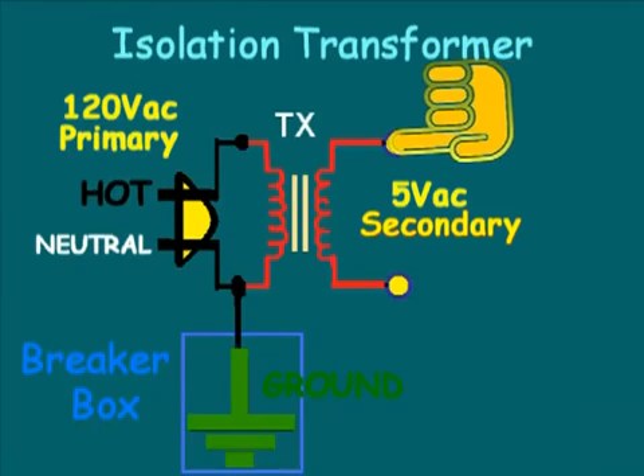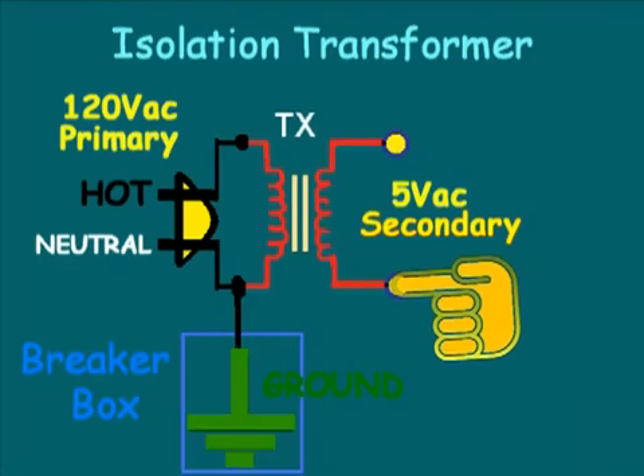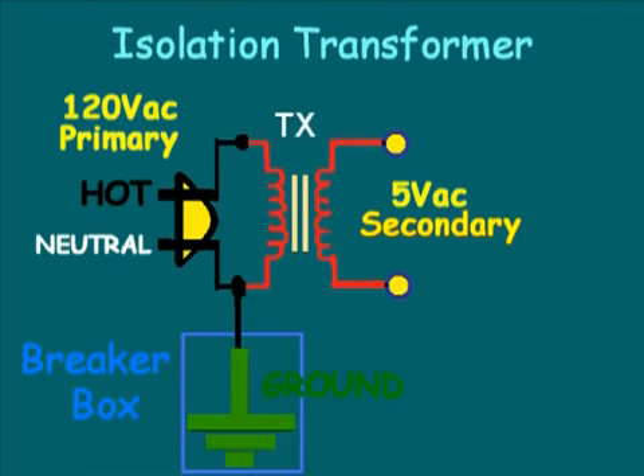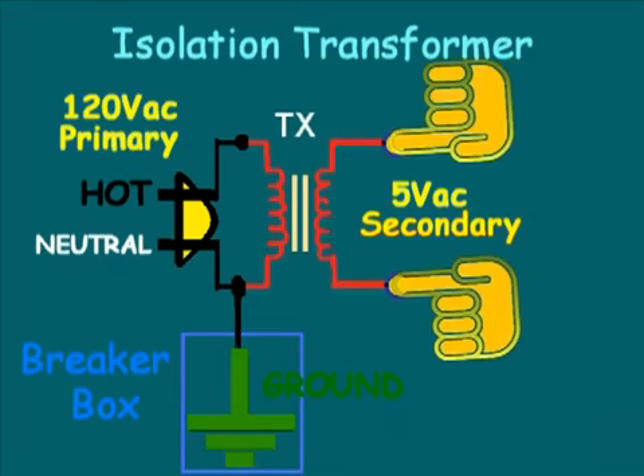However, touch either secondary leg and you won't feel a thing. That's because the secondary does not seek ground as a return. The return is from one secondary leg to the other. To receive a shock, you'd have to touch both secondaries at the same time.